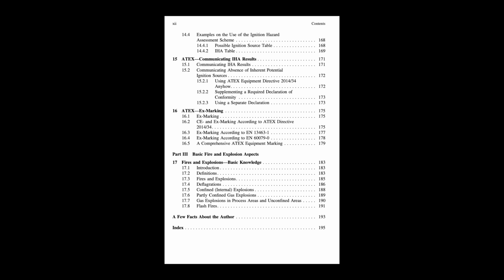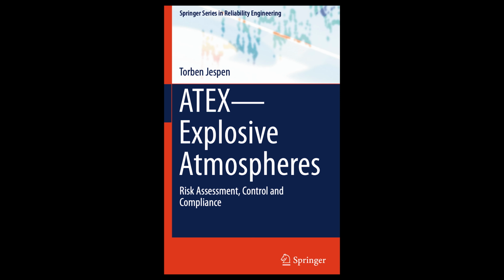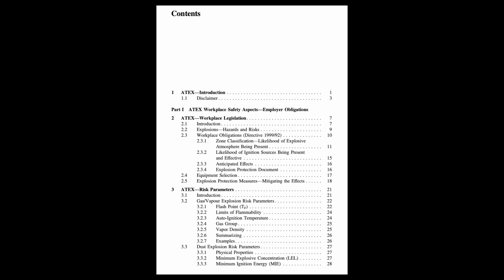Not exactly groups, but a key parameter is the minimum ignition energy, or MIE. This measures how sensitive a dust cloud is to ignition by an electrical spark. And why is MIE so important? It's absolutely crucial when assessing risks from static electricity discharges and also from potential mechanical sparks. If a dust has a very low MIE, even a tiny static spark that you might not even feel could be enough to set off an explosion.